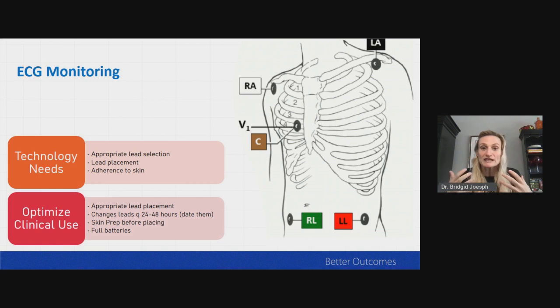So, a 12 lead includes arms and legs for monitoring, and obviously accurate electrode placement is key, but if you have somebody continuously 12 lead monitoring, it's always going to have artifact, right? They can't stay still forever. So 5 lead gets us as close as we can get to getting a 12 lead continuously. So we want to make sure that we have the leads in the correct placement to identify arrhythmias if they're there, plus a decrease in false alarms. So that's going to help us with our alarm management as well.